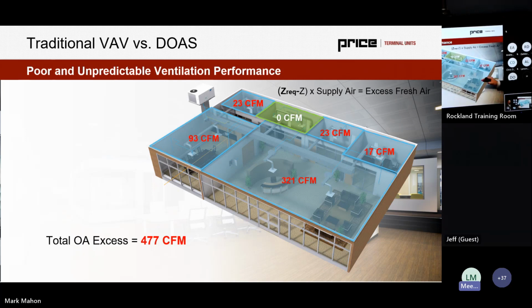The ASHRAE DOAS Fundamentals Design Guide Handbook has a paragraph or two that references that, but it doesn't go into detail on all the options for the traditional VAV design, because that's more covered in 62.1, in 55, and also in the ASHRAE Handbook of Fundamentals. But it's a very good point. This isn't necessarily just lost to the environment. And just to close that out, for everyone online, the question was, can we not put that excess outdoor air back to the return and get a credit for it? And the answer, much more briefly, is yes, you can.